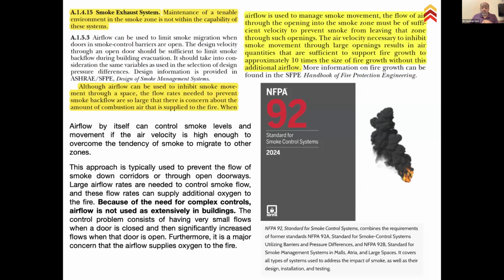My dear friends, if you really look, 92A talked about barriers, meaning you create isolated compartments for exits. It talked about pressure differences, so it talks about PD. It doesn't talk about ACPH. The 92B is basically for large spaces like malls, atria, airports, convention centers, those spaces with very high ceilings where you have issues mitigating smoke. But it does not talk about a smoke control system for offices.